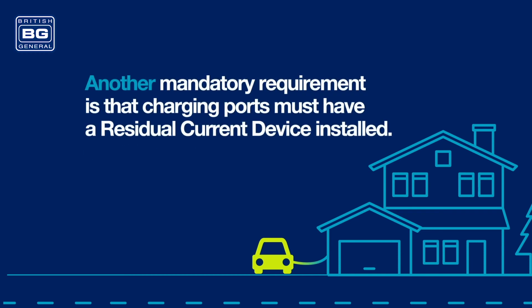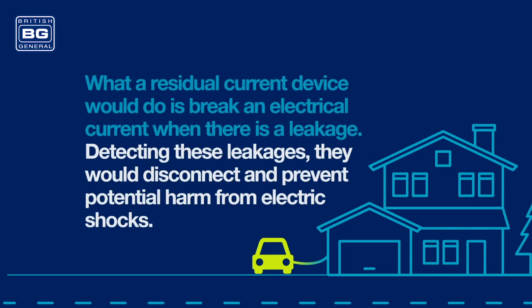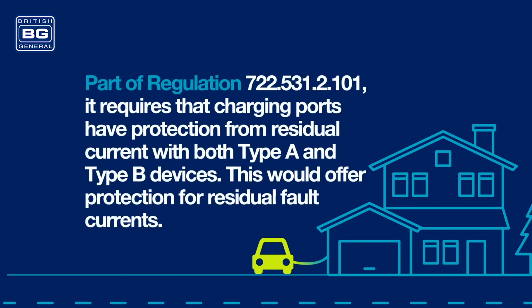Another mandatory requirement is that charging ports must have a residual current device installed. What a residual current device would do is break an electrical current where there is a leakage. Detecting these leakages, they would disconnect and prevent potential harm from electric shocks. Part of the regulation 722.531.2.101 requires that charging ports have protection from residual current with both Type A and Type B devices. This would offer protection from residual fault currents.